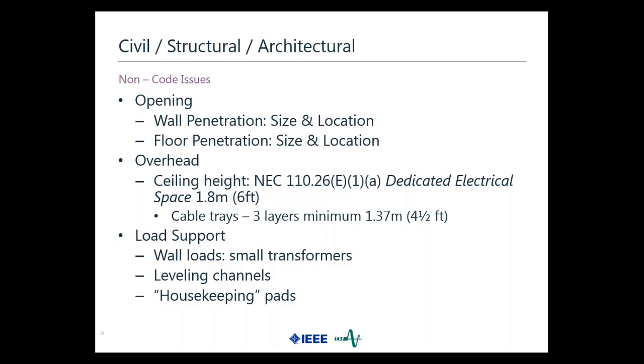It's not required that it be 6 foot, but if you have that much available, you need 6 feet of dedicated electrical space above MCCs, switchgear, panel boards, etc.